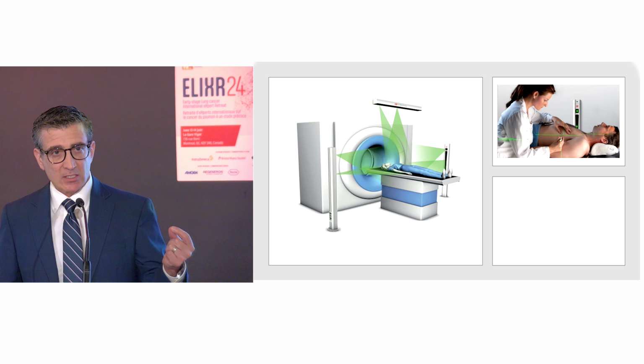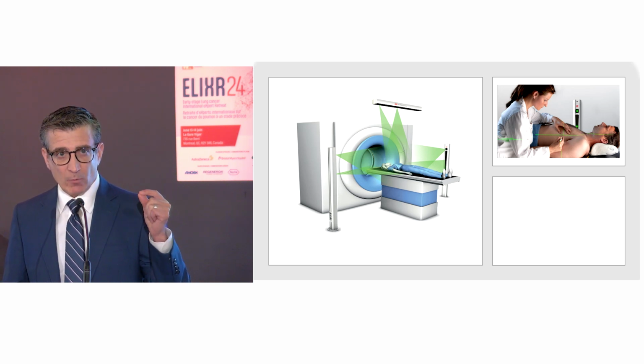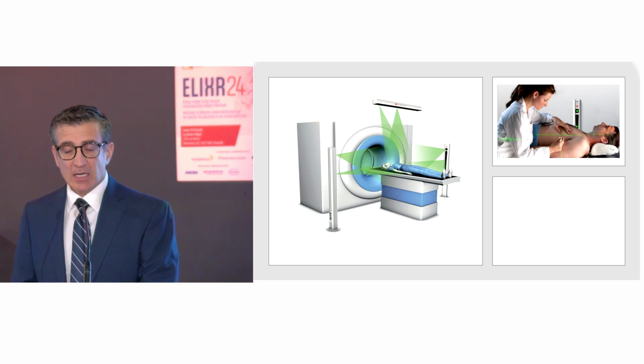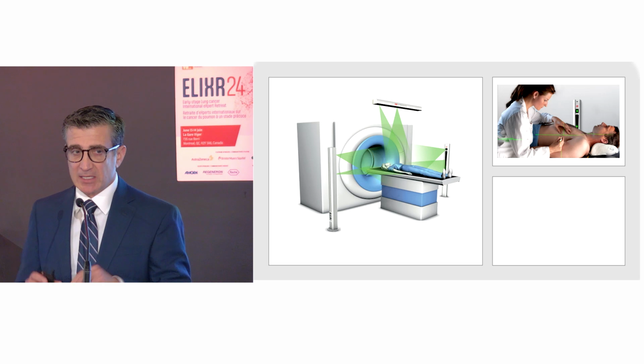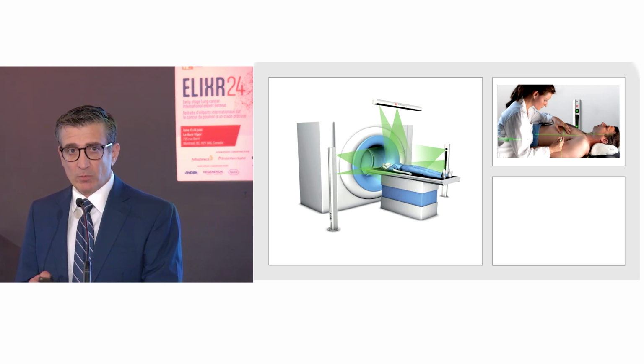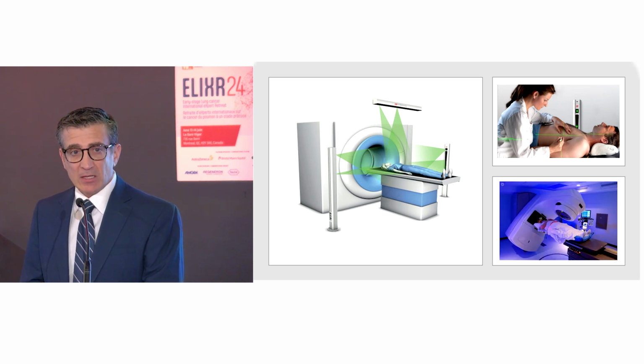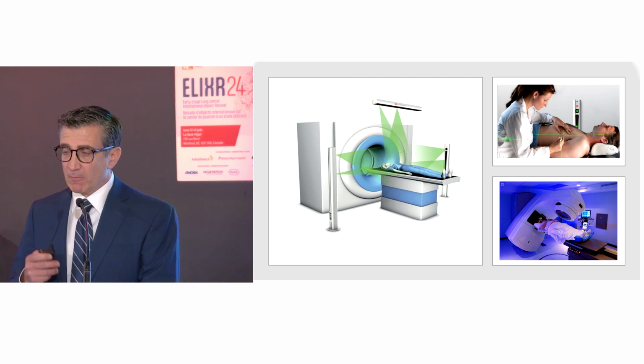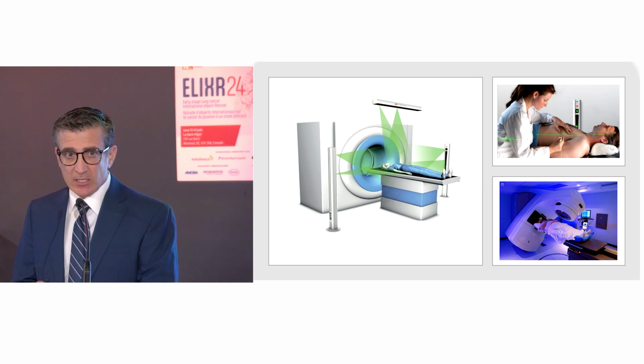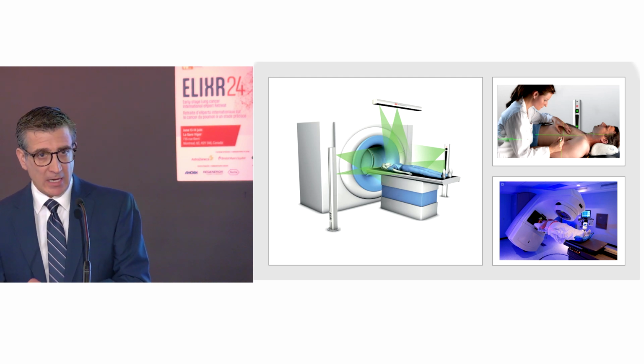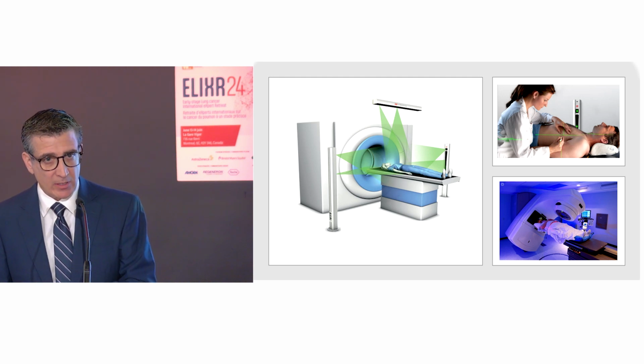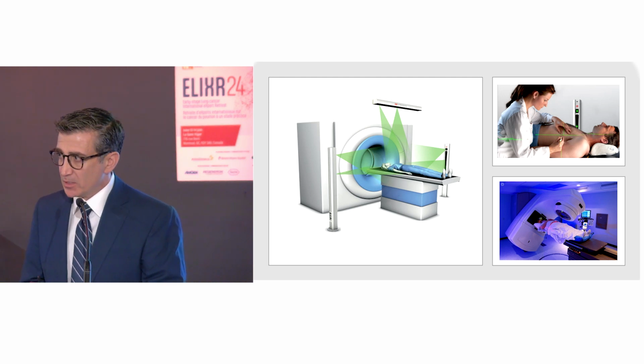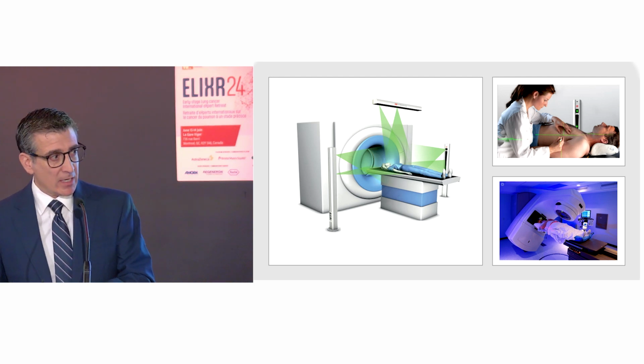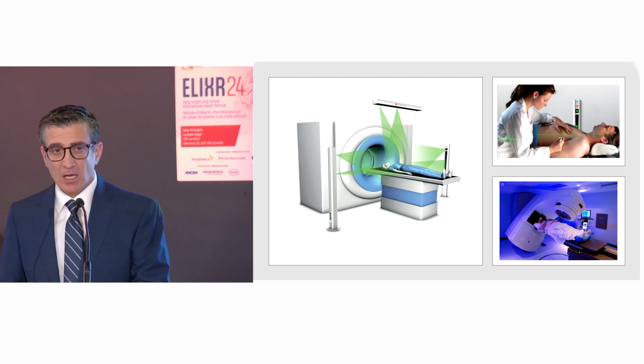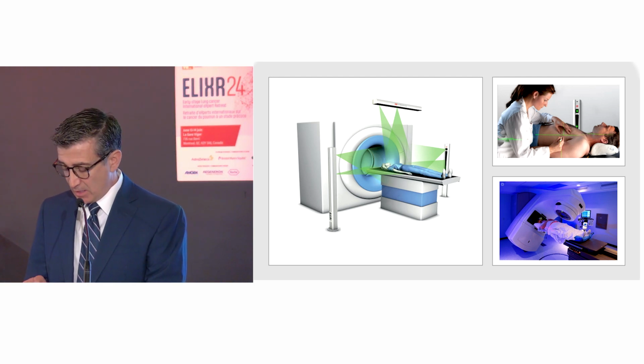It has to be less than 1 millimeter of reproducibility every single day. And this is where our patients sometimes get tattooed, and we tattoo according to these laser lines. And then the patient comes back to the room, and the laser lines are also all aligned to this isocenter. And I just want to remind, I have intentionally put a picture of a linear accelerator that does not have a cone beam CT. So if you want good image guidance, make sure that the therapeutic machine has a cone beam CT.